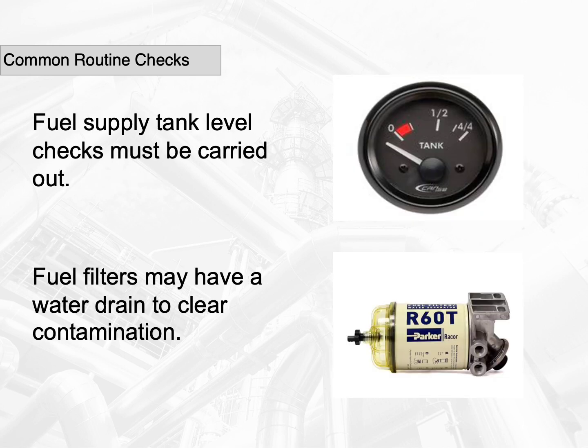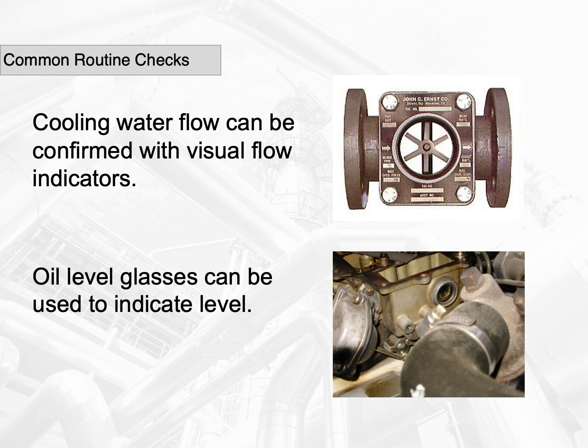Fuel supply tank level checks must be carried out. Fuel filters may have a water drain. To clear contamination, fuel supply and filtering is critical. Running a system dry of fuel can cause restart problems with airlocks. Visual checks can assist in positive confirmation of flow and level. Cooling water flow can be confirmed with visual flow indicators. Oil level gauges can be used to indicate level.